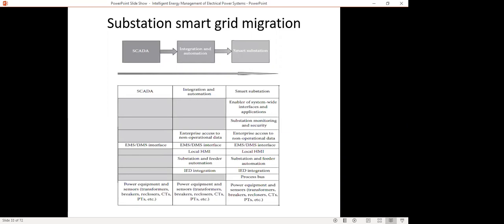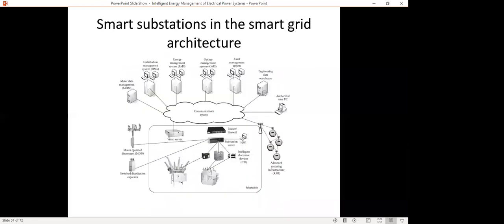The SCADA has the energy management systems and the distribution management systems, DMS. Then it has the power equipment sensor data, like transformers, breaker positions, recloser positions, current transformers, and potential transformers information. This information is transmitted to the smart substation. So when we are integrating automation in the power systems for smart grid operations, the smart substations enable system-wide interfaces and applications, substation monitoring and security, enterprise access to non-operational data, EMS and DMS interface, local human machine interface, IED integration, and the process bus. So we can bring all this into the smart substations.